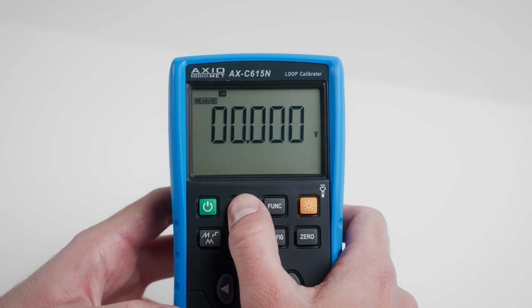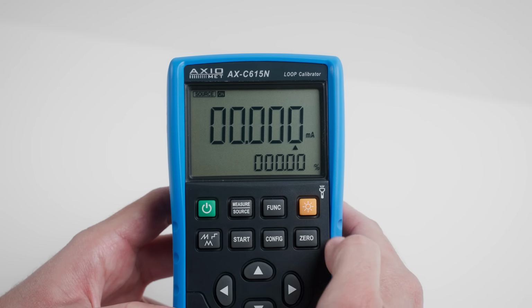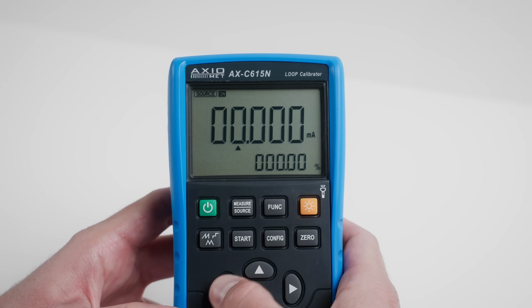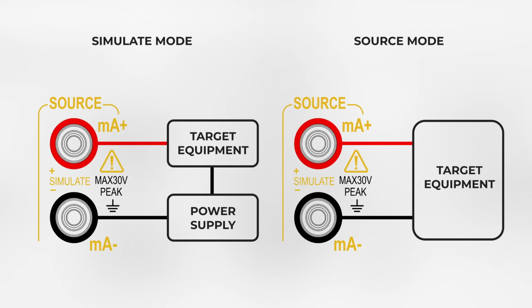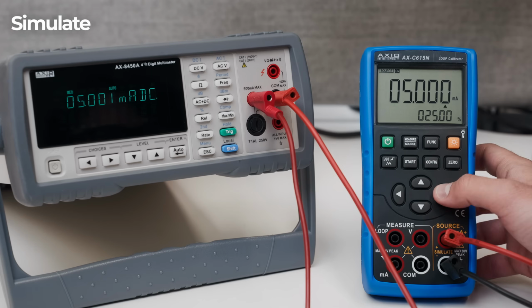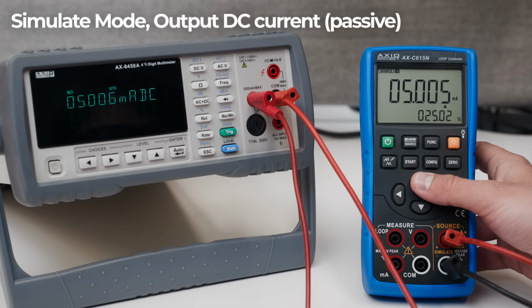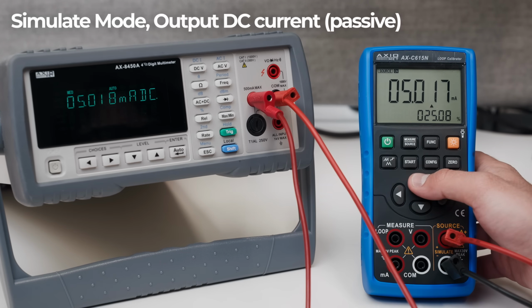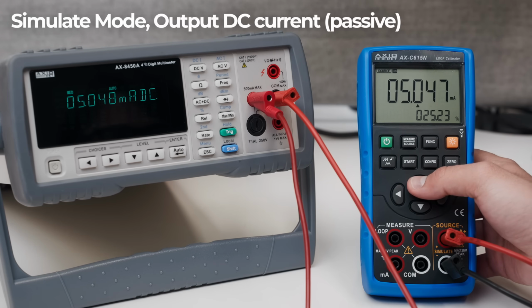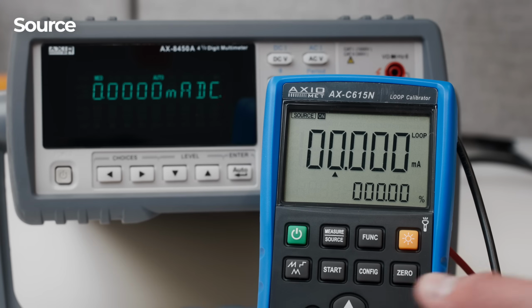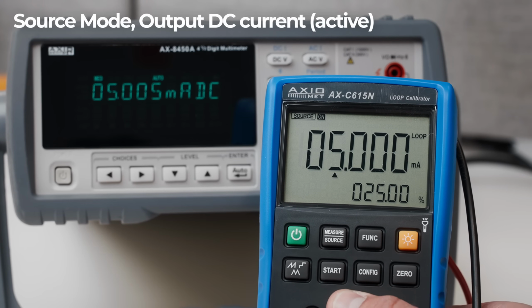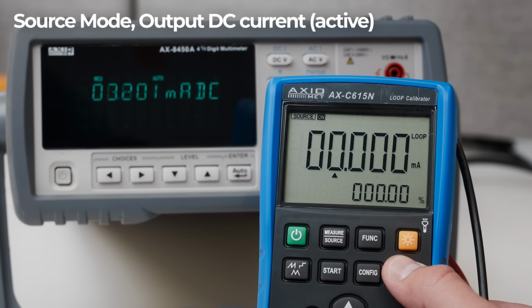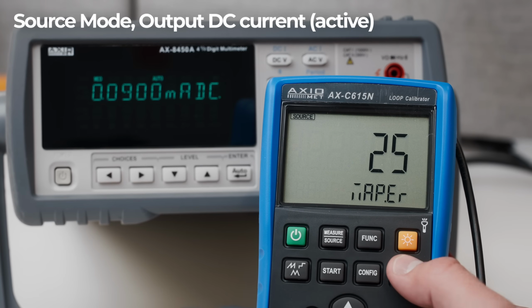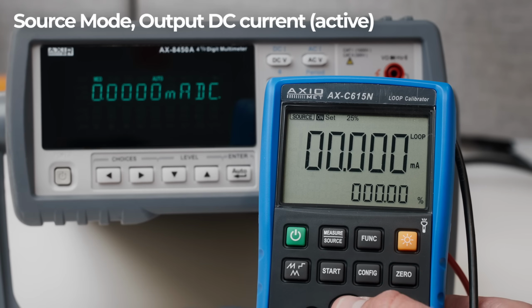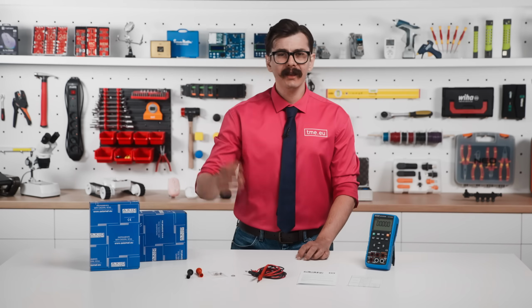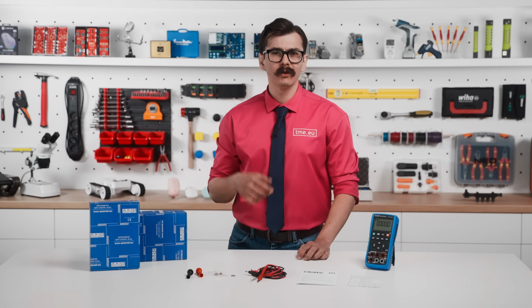In source mode, you can switch between source and simulate by pressing the function button. In both cases, the goal is usually the same: testing the receiver, such as the PLC input. But the difference between those modes depends on who provides the loop power. In simulate mode, or as stated in the manual, output DC current passive, the loop is powered by an external 5 to 28 volts DC power supply. The black probe connects to the power supply and the red probe connects to the PLC or the receiver. In source mode, the calibrator actively generates the current signal. You will also see the loop indicator on the screen. In this mode, the calibrator injects the current signal directly into the receiver, which makes it useful for testing PLC analog inputs or controllers. To make your life easier, the AX-C615N provides several ways to control the output current.